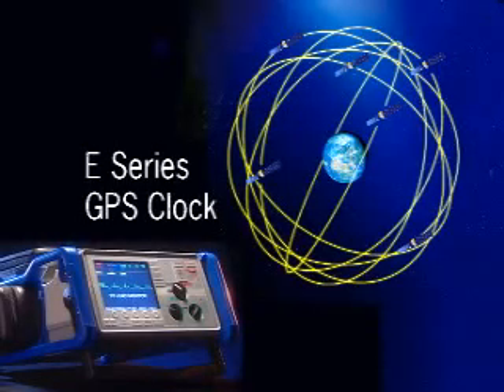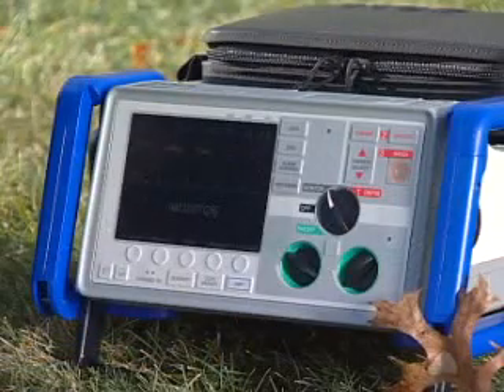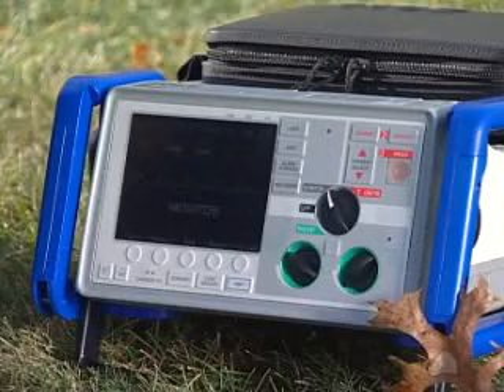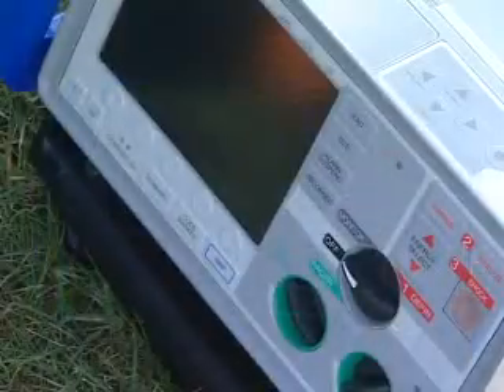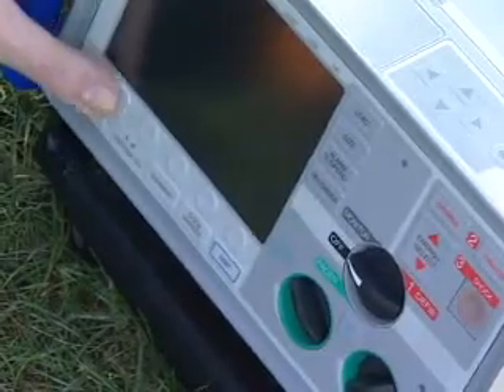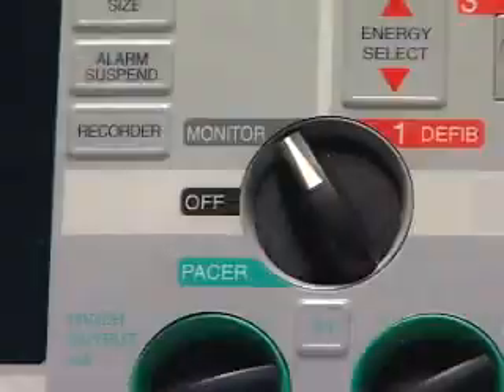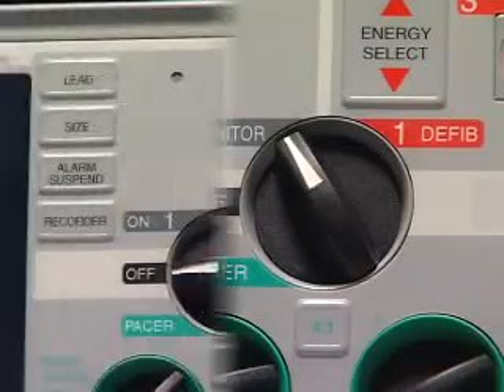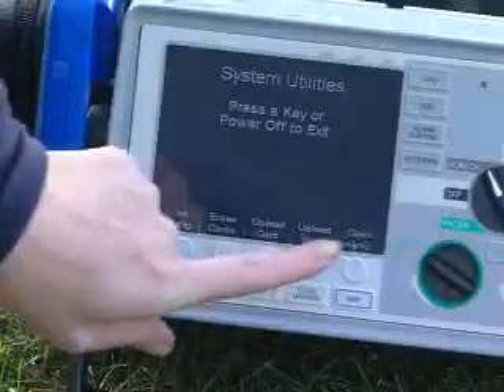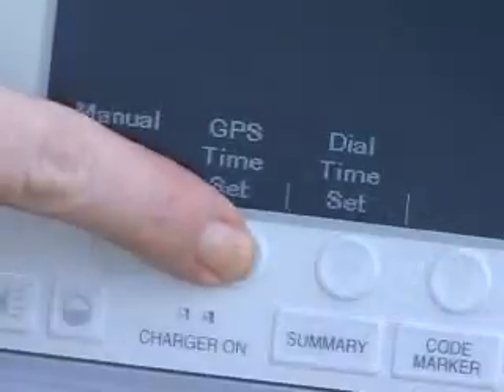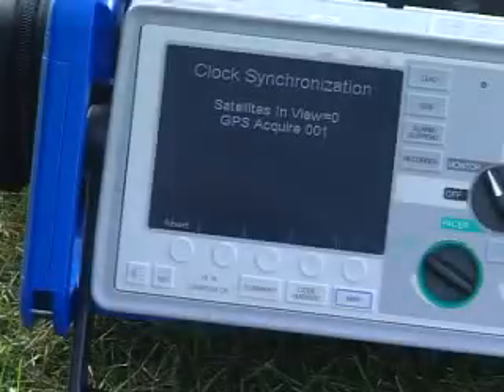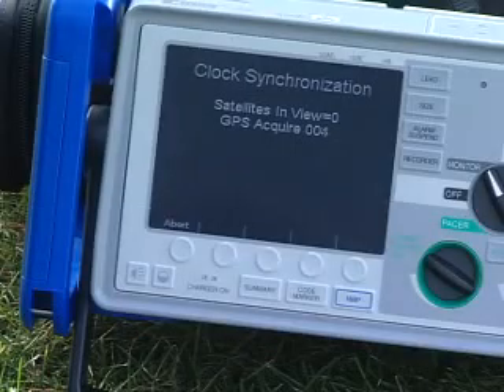All E-Series defibrillators are equipped with an internal GPS clock to assure accurate times whenever the device is used. Placing the device outdoors when performing the GPS synchronization is recommended. To manually access the setting for GPS, press and hold the leftmost soft key, while turning the selector switch to Monitor, or On for AED models. When the System Utilities screen appears on the monitor, release the soft key. Press the Clock Sync soft key, then press the GPS Timeset soft key to display the GPS clock synchronization screen.